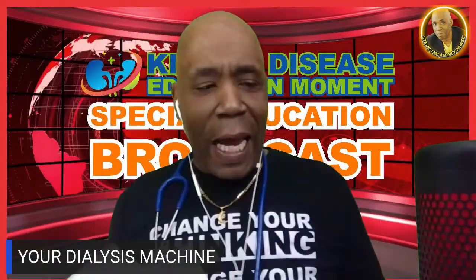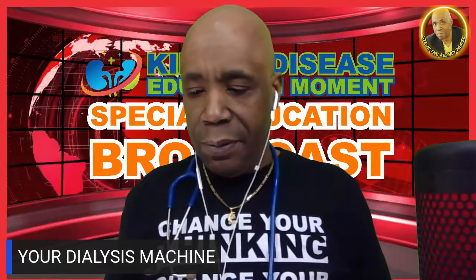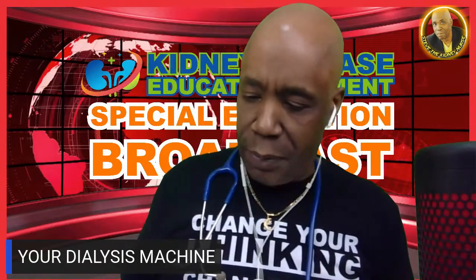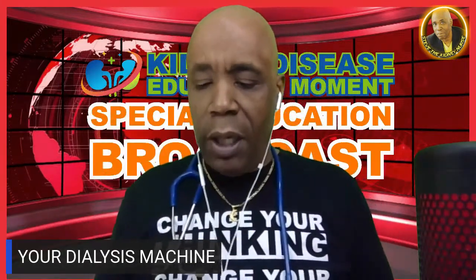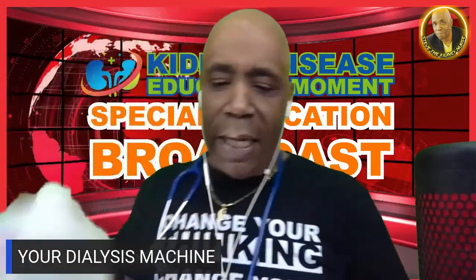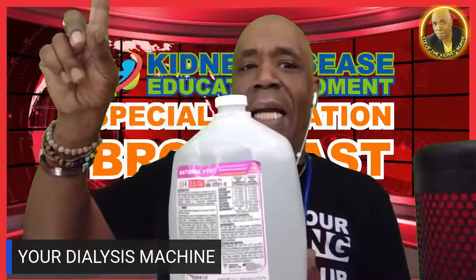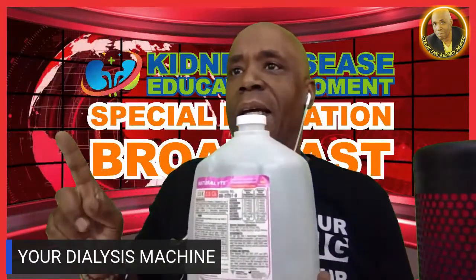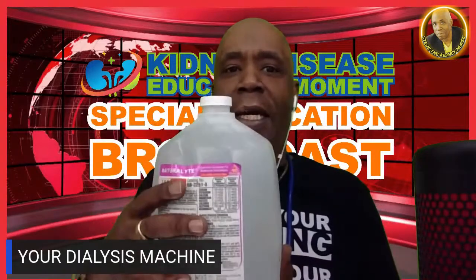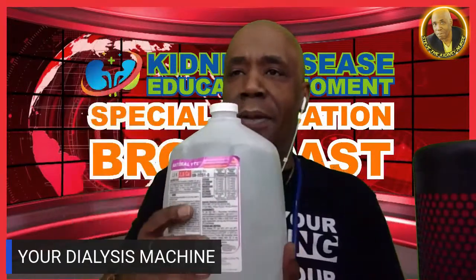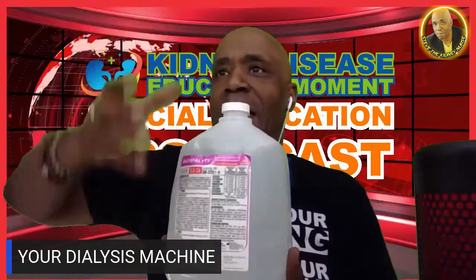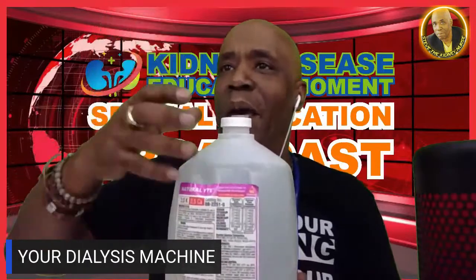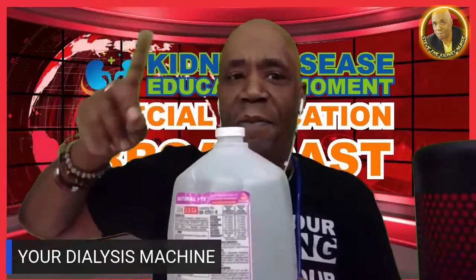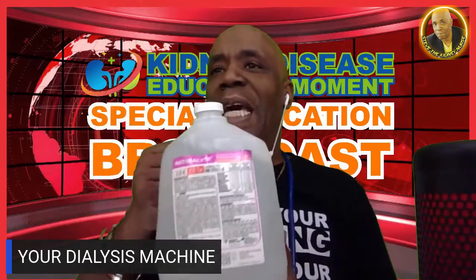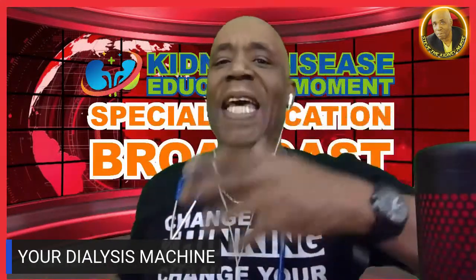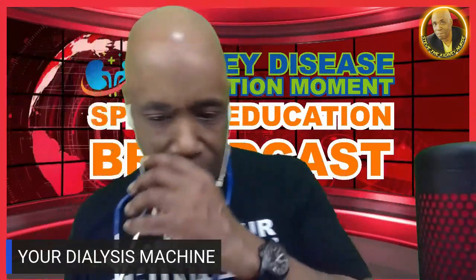Now let's move on with the dialysis machine. And so, as I was saying, the used dialysate goes out of the red line, and the fresh dialysate, the bath right here, comes through the blue line, right? But it doesn't get in contact with the blood because you have a membrane that you cannot see in that filter. You have a membrane you cannot see that separates the blood and the dialysate. Okay?